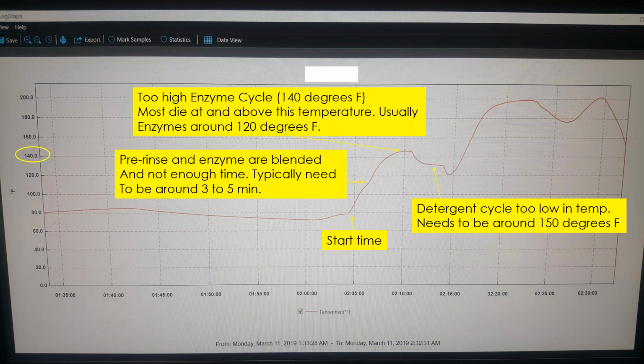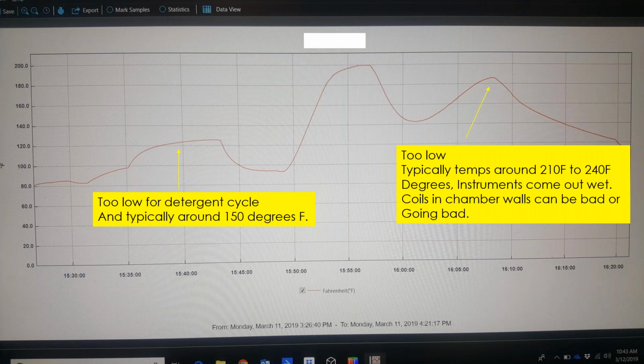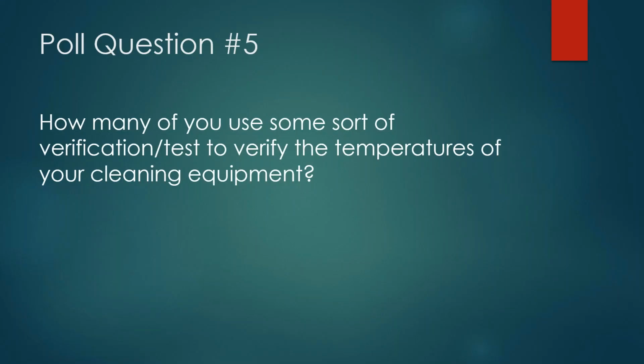So here you can see there are ways to gather this data, and you can see sometimes that enzyme rinses become too high, and enzymes can actually be killed by that being too high. Pre-rinses can be too short, and the detergent cycle is a little too low in this graph. And to finish out the cycle here, this is too low on the dry phase. And this could be because of chambers or issues like that, but you're going to end up with wet instruments for that.